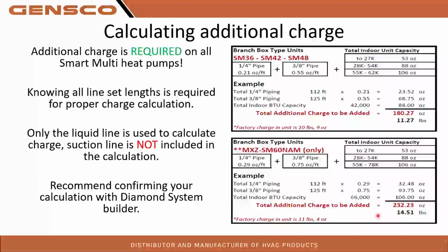On average, I see on the small side, usually I'd say 7 to 8 pounds additional charge required for your systems. And yeah, I have seen some pretty good sized systems with lots of indoor equipment, lots of line sets that can get up to that 14, 15 pound mark. So this is also going to be something important for you guys to remember on your sales side or your bid side. Anytime you're doing smart multi, refrigerant isn't cheap. That stuff is getting pretty darn expensive. And if you're not planning for that on your bid of having an additional 15 pounds of charge, you're probably going to be losing out on a couple hundred dollars worth of refrigerant that's going to be required for that system to run properly.